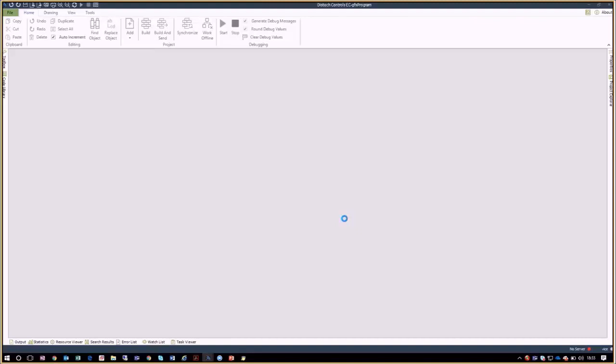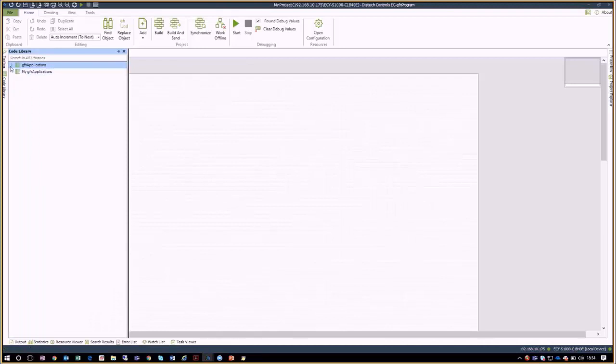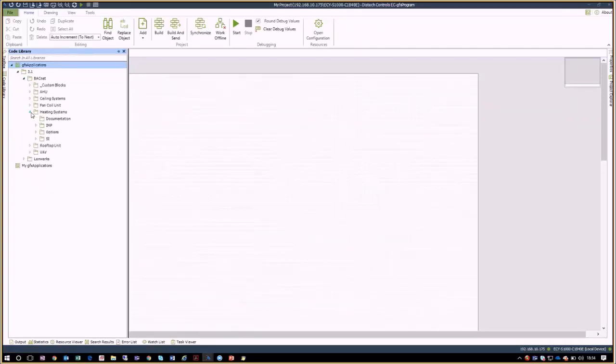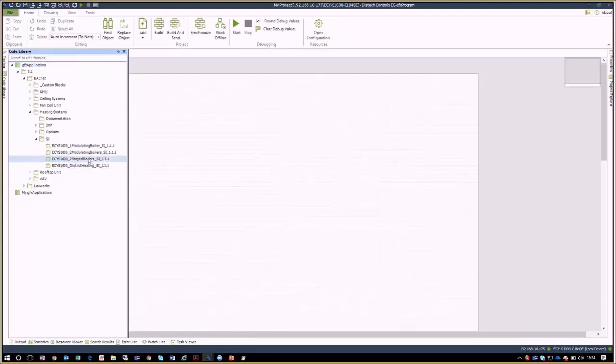Since this controller is a new controller, we are going to open a new project and load a preloaded code. To do this, we are going to go into Code Library, GFX Applications 3.1 and then choose the network type that we have. There are multiple codes for different applications available. For our case, with an ECLYPSE S1000 controller, the objective is to create an application for boiler rooms. Therefore, we will use the code for a two-stage boiler room. You only need to drag and drop this code onto the blank programming sheet.